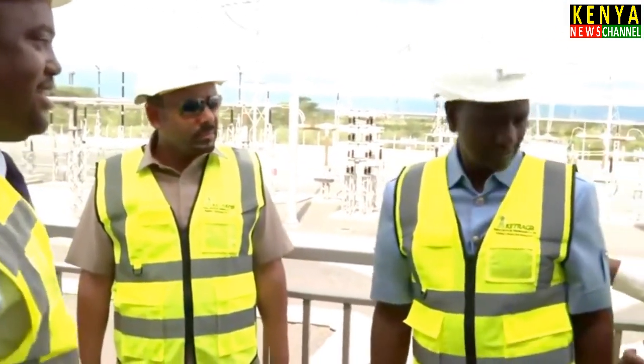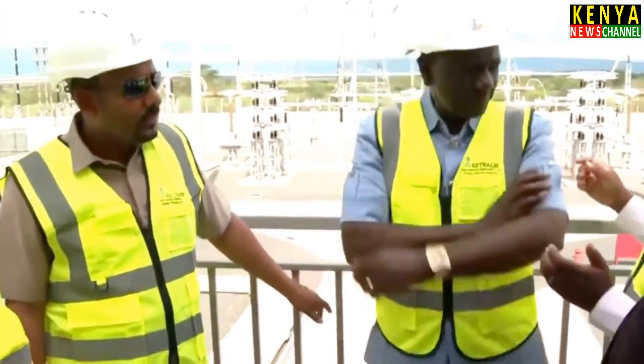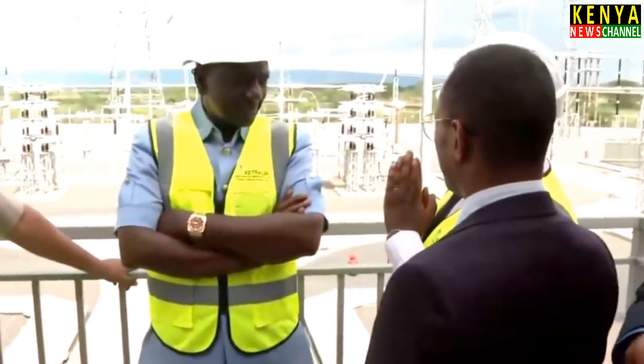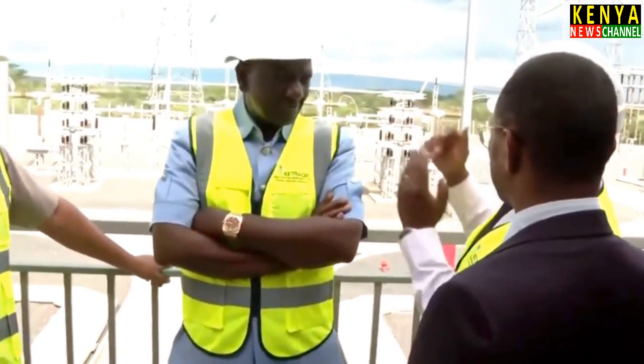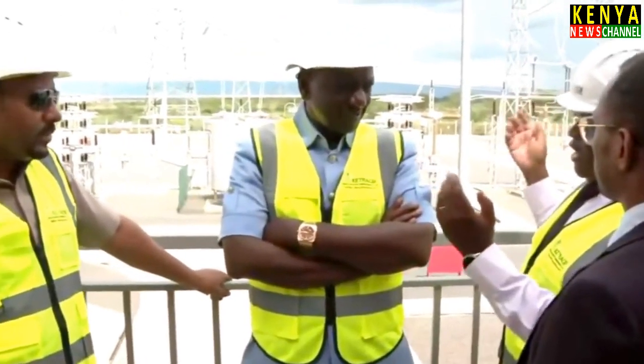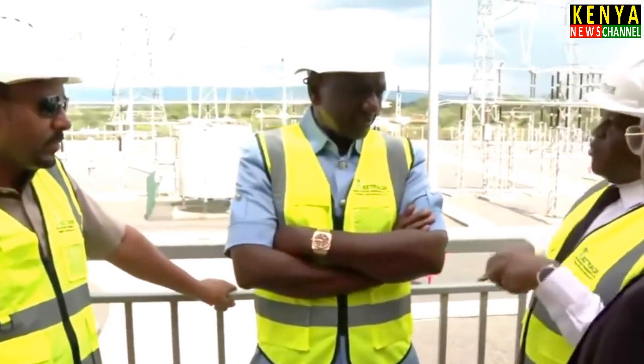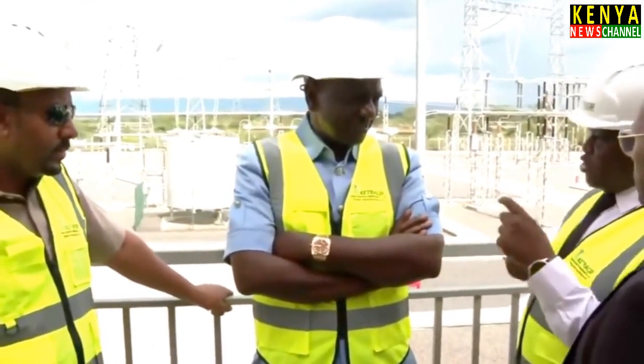There are two poles to bring power from Ethiopia in the HVDC system. We say the capacity is 2,000 megawatts, meaning one pole can carry 1,000, the other pole can carry 1,000. Now with the DC system, you have to return the power, like a battery circuit, it has to be completed.